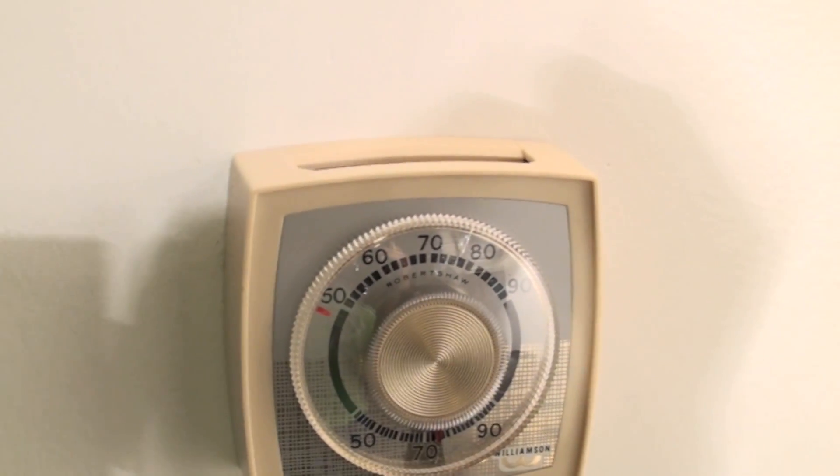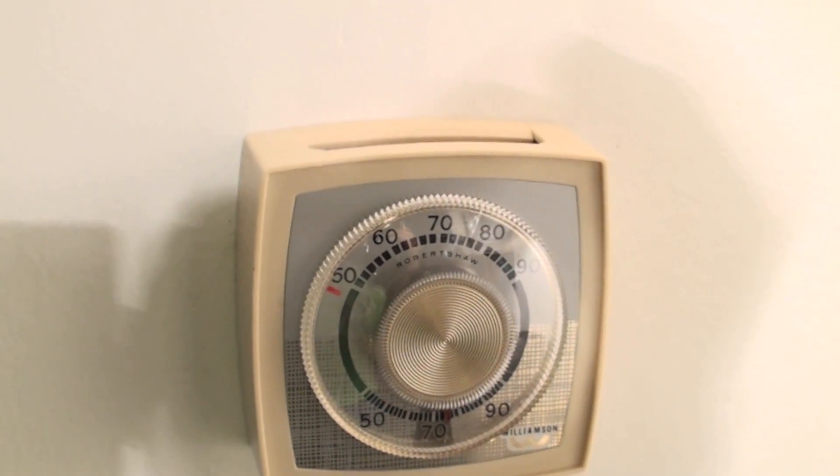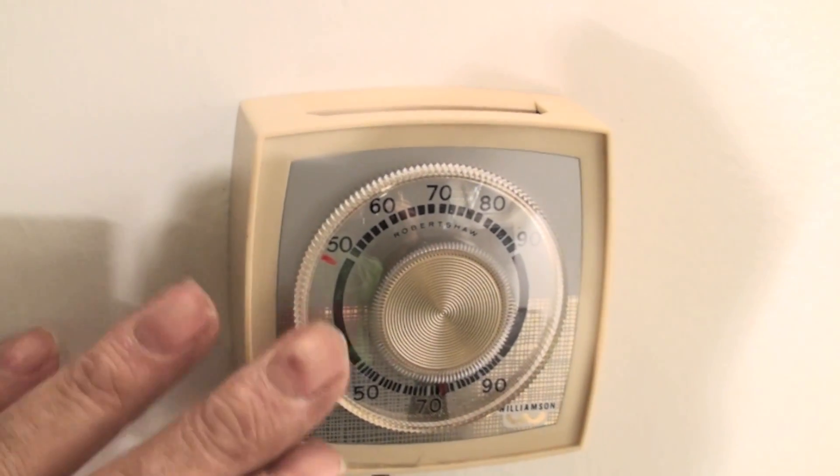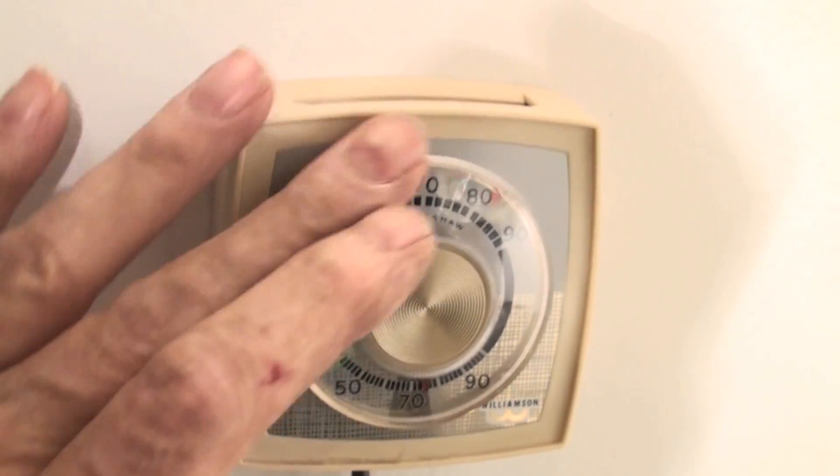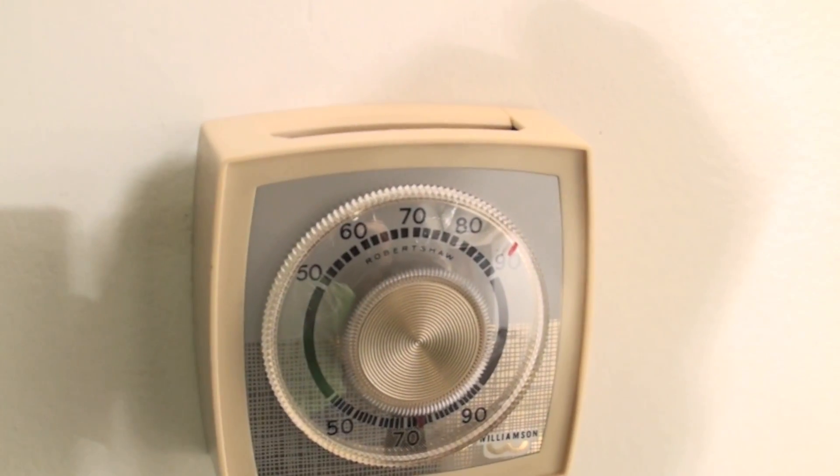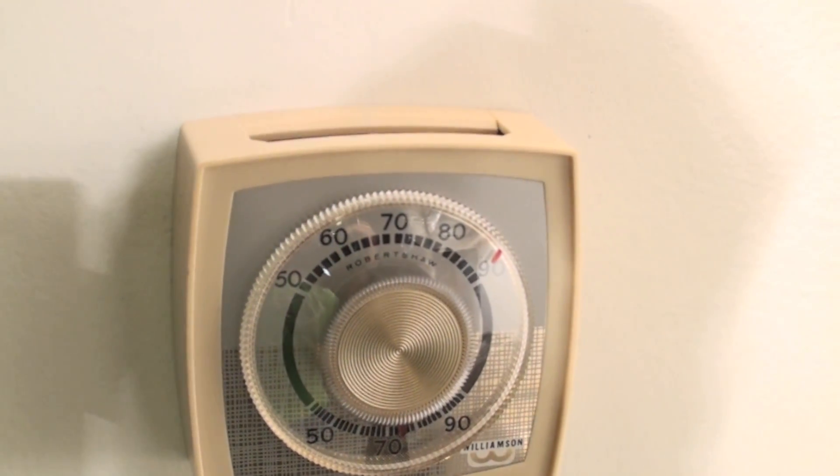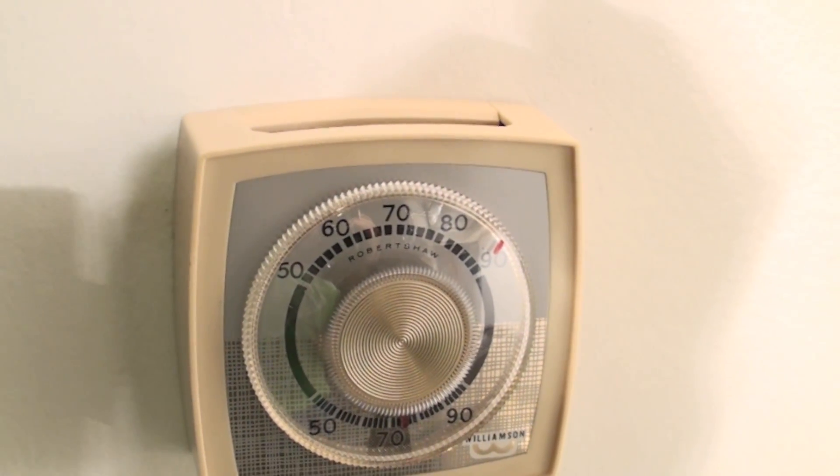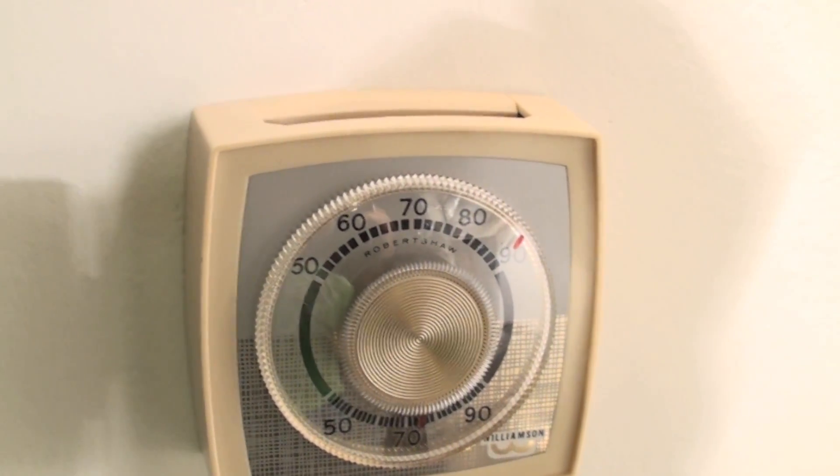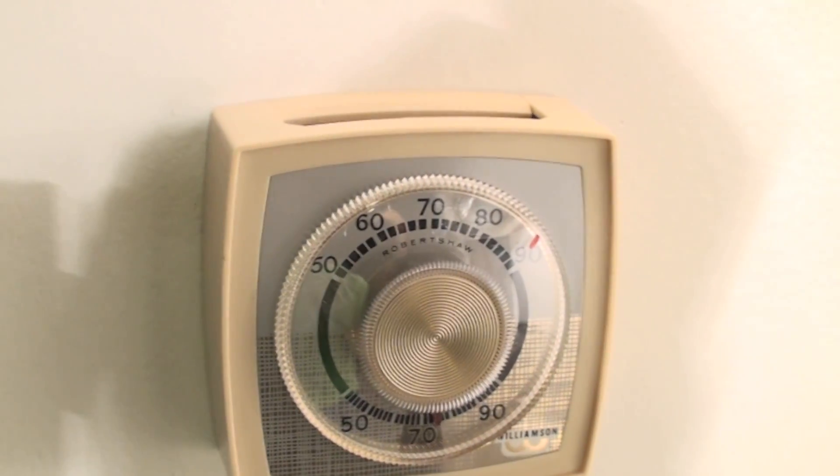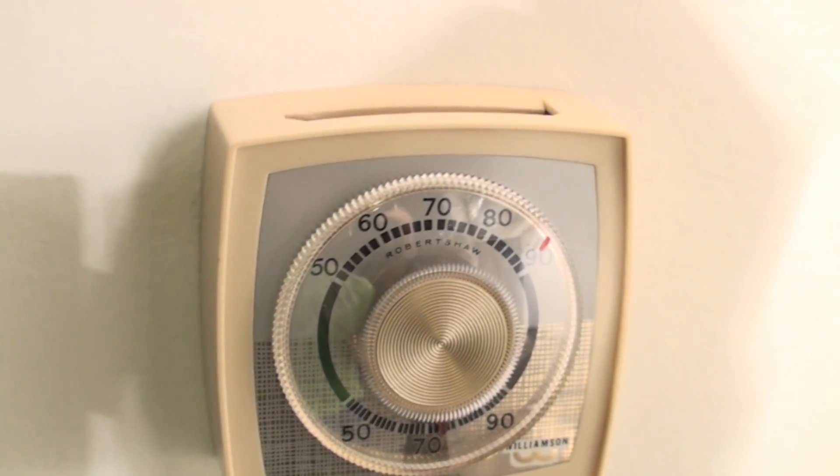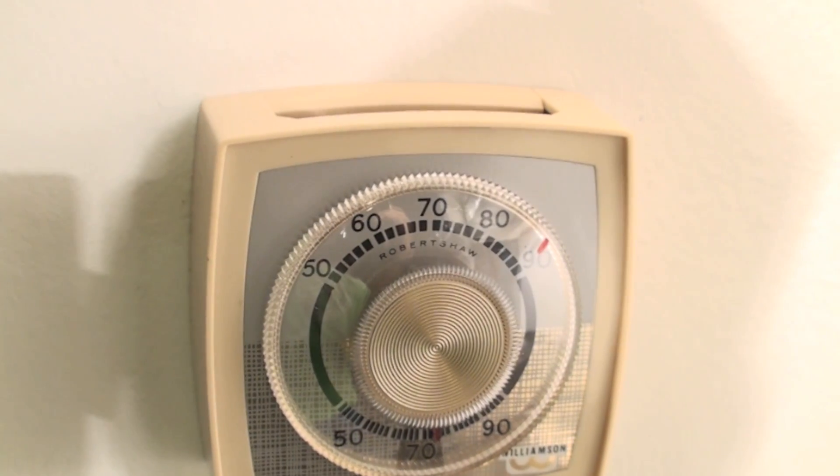Servicing the 80% furnace. The first thing you're going to do is go to the thermostat and turn it all the way up. Now this is in the same room, so obviously the inducer just came on.